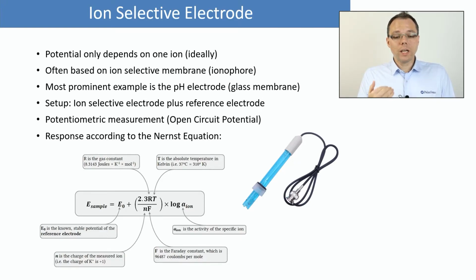However, you do get then a logarithmic reply between concentration and potential. And you see, of course, that means you have to carefully choose your measuring range, and you should pay attention if there is a certain range on your ion selective electrode advised to use.